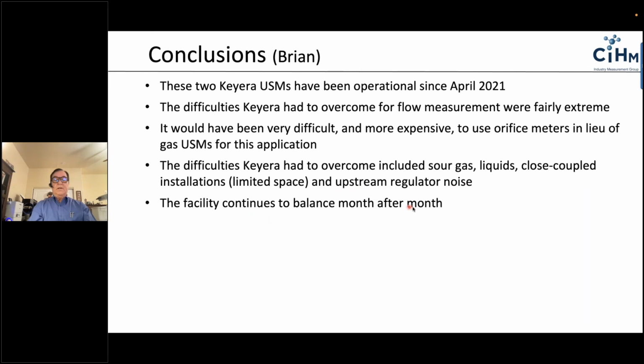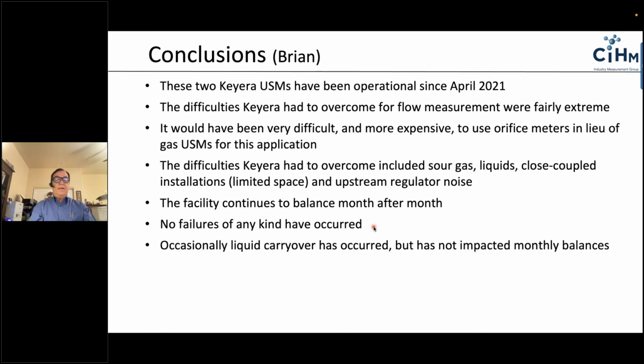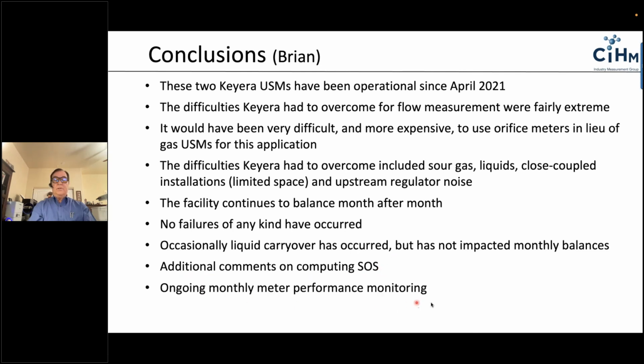The facility continues to balance month to month. No failures have occurred of any kind. Occasional liquid carryover has occurred, but it has not affected the monthly balance, and the meters continue to operate accurately. I'll let Brian talk about some additional comments on the speed of sound as well as the ongoing performance monitoring.